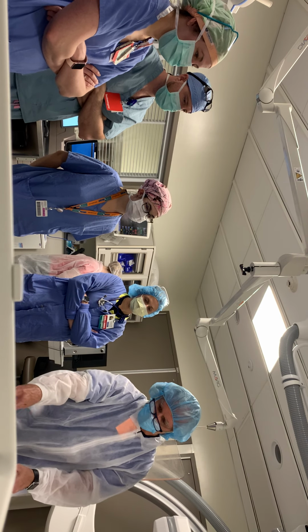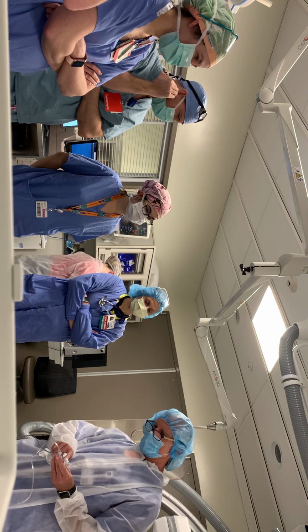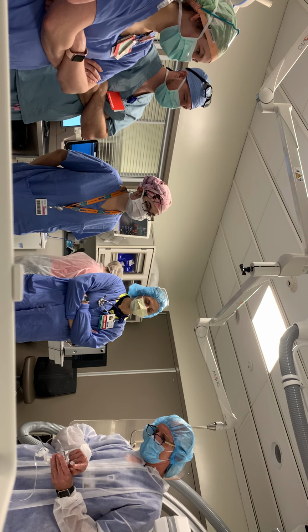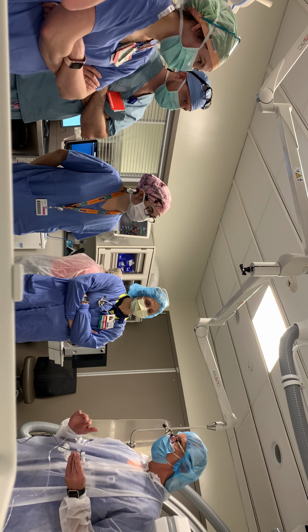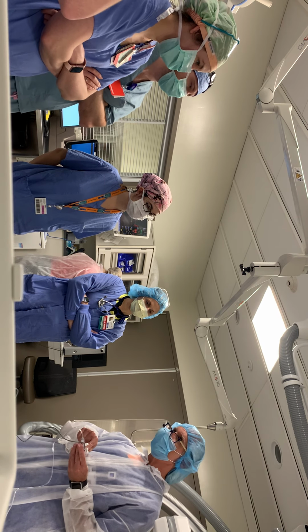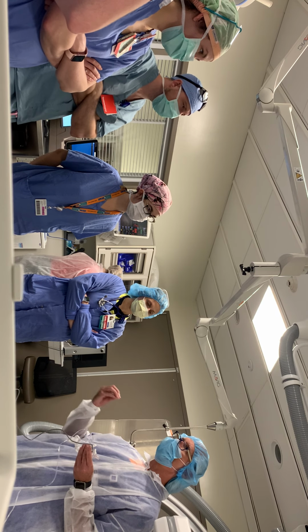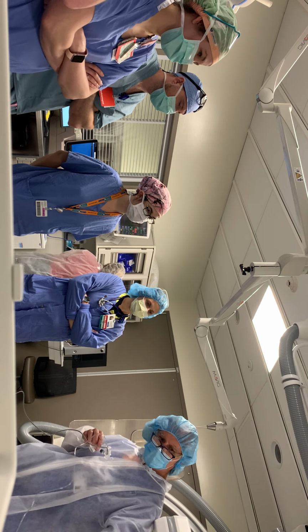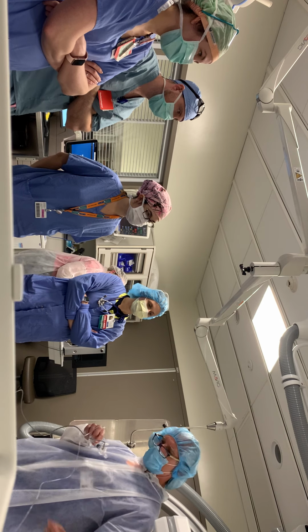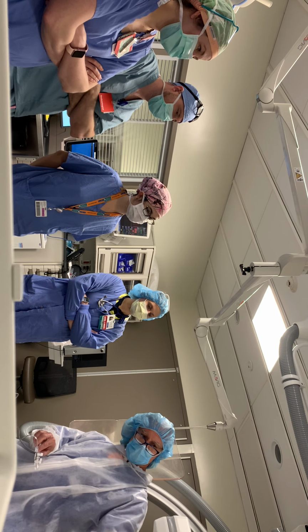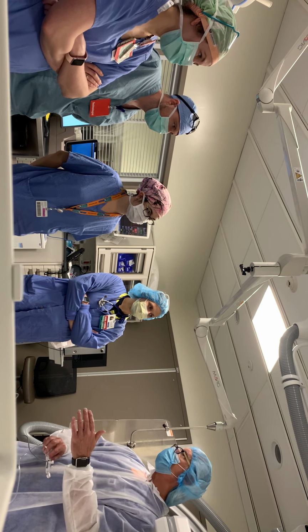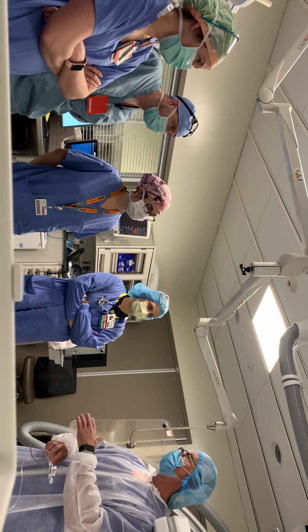With this one, it makes a big difference. If I'm trying to 0 from this port, I'm not 0'd. Because at this point, this transducer is sensing all the weight of the fluid in this line. So unless these are absolutely at identical level, then you're baking into your 0 either a positive or a negative.